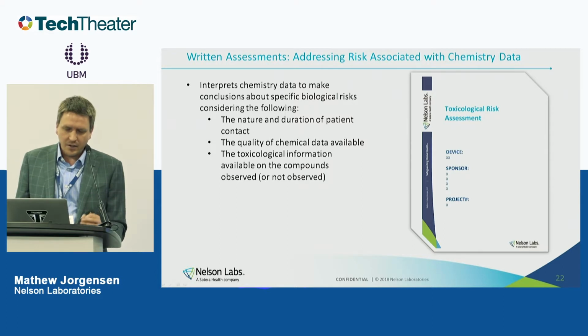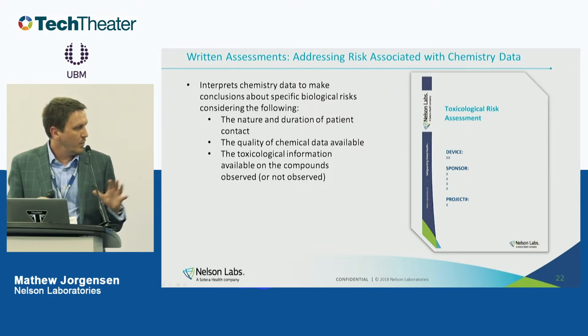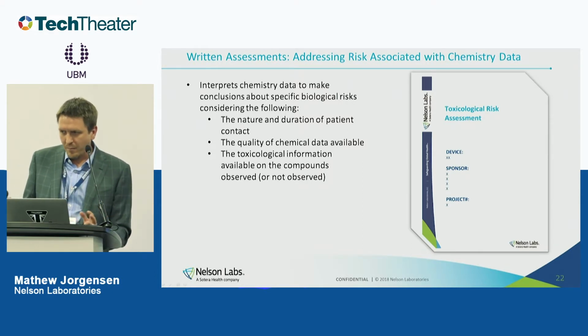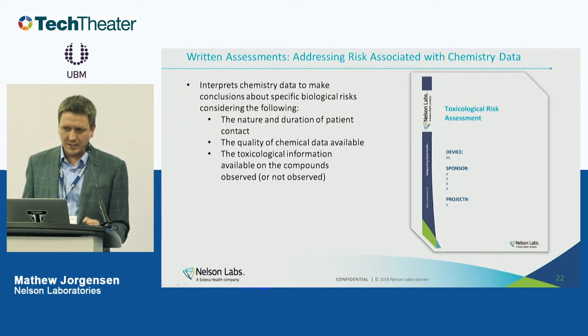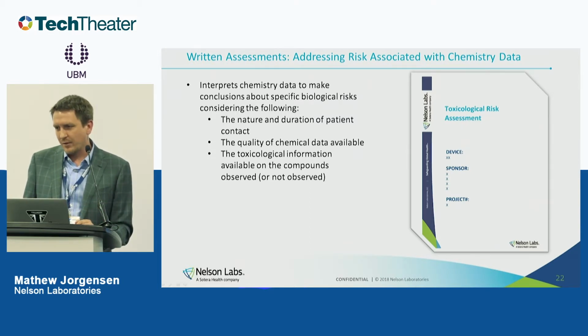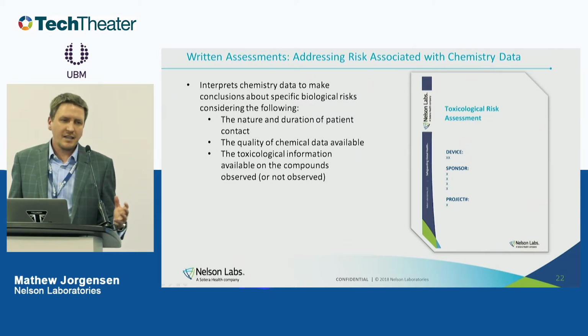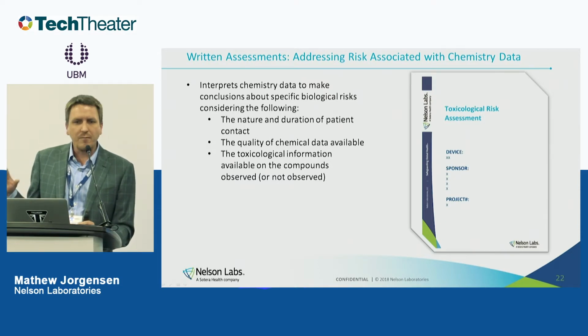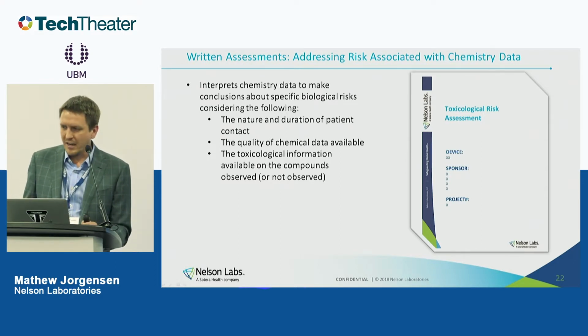So the toxicologist will make specific claims about carcinogenicity and genotoxicity and so on based off of these results. Now, the reason why I want to bring this up here, and I'm going to talk about chemistry a little bit just because I can't hold myself back, is that as you go through this process of becoming compliant with the MDRs, you could have some cases where you have very minimal testing, but more often than not, you're going to be in the case where you have limited data available and you'll have to do chemistry testing and a toxicological risk assessment. It's actually pretty likely that happens.